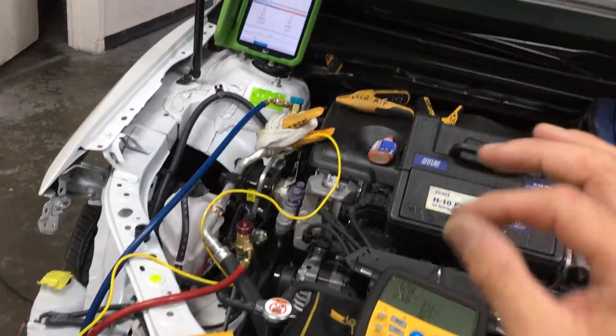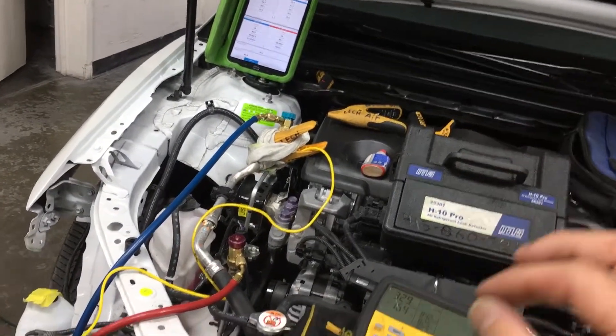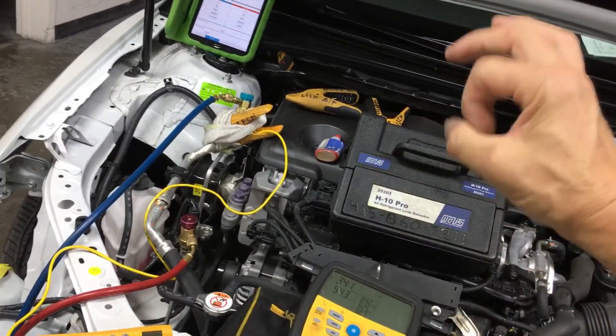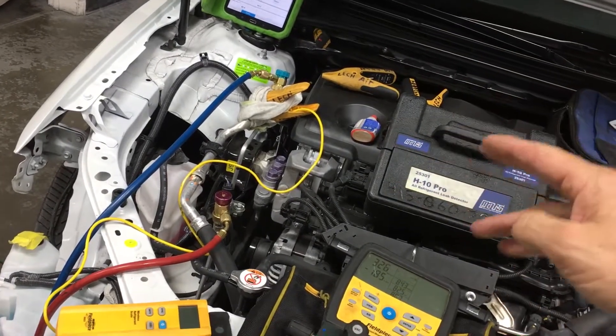The low side draws down, it drops just past the expansion valve, it flashes below the temperature at which water freezes, and you get a little dam of ice crystals that build up in there.